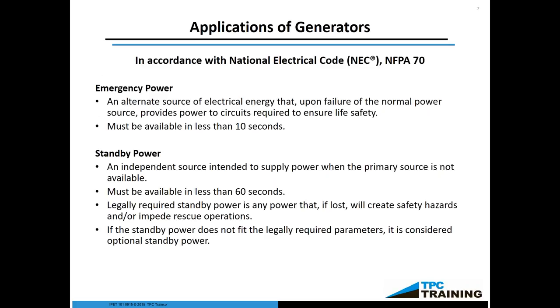In the NFPA series, specifically NFPA 70, they define emergency power as an alternate source of energy that provides power. The key part is that what constitutes emergency power is that it must be able to come online and accept the load in 10 seconds. This is one of the primary reasons why diesels are used for emergency power. Assuming you can keep the engine warm — usually with some type of block heater or oil heaters — a diesel engine can accept the load in less than 3 to 5 seconds, well within the 10-second standard.